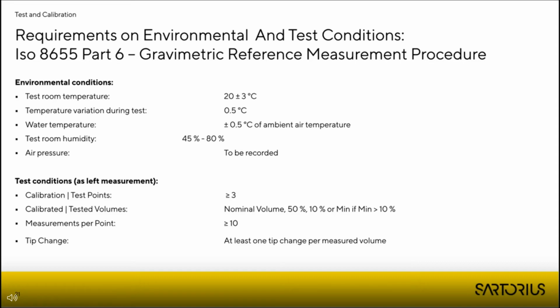The test conditions. A calibration under Part 6 requires at least 3 calibration points, and the 3 calibration points must be at nominal volume of the pipette, at 50% of nominal volume, and at 10% of nominal volume. As pointed out earlier, at least 10 measurements per volume are required here. And last but not least, tip change, and this is something quite new in the new ISO. The new ISO requires at least 1 tip change per measured volume.